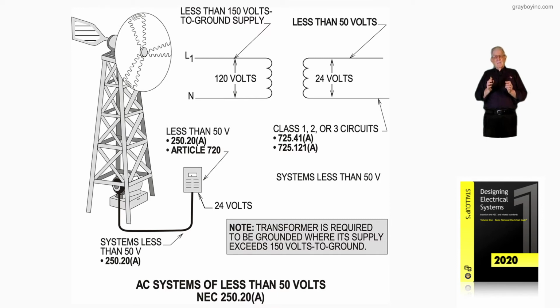But this goes on for any kind of power that is less than 50 volts, and you feed, as the note says, you feed that primary. And as long as you're 150 volts or less to ground, you don't have to ground the secondary at all. Now, I'll give you another example. Say that you had a transformer, as you see in the illustration, a little low voltage transformer, and you bring in 120 volts, and you take out 8 volts, 12 volts, 16 volts, 24, whatever you need for your chimes.